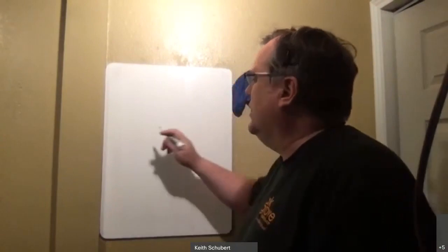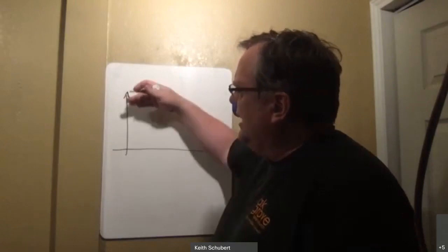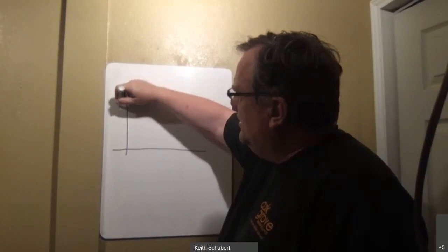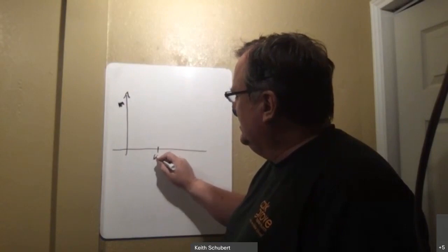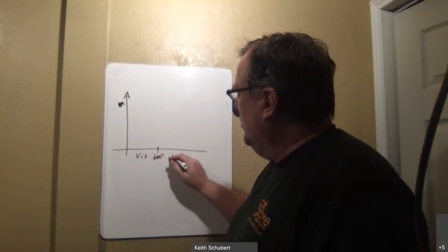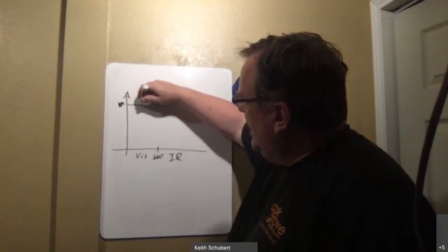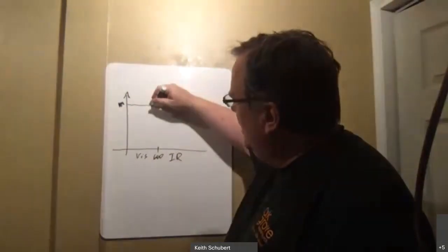And the difference is that not all the wavelengths of light penetrate through equally. So if you plot the percent absorption, and it's based on a distance you've traveled, but let's just worry about the percent absorption, versus wavelength, right? So 660 is like the end of red. So if we have the visible light here and we're going into the infrared portion, for most of the visible light, your skin is completely opaque. That's why people can't see through.